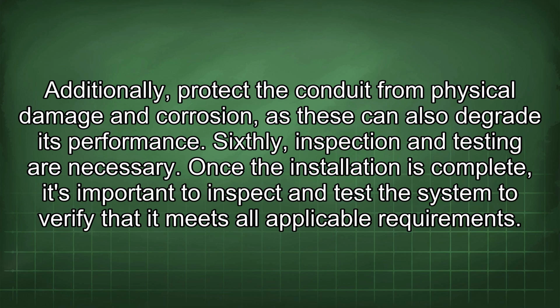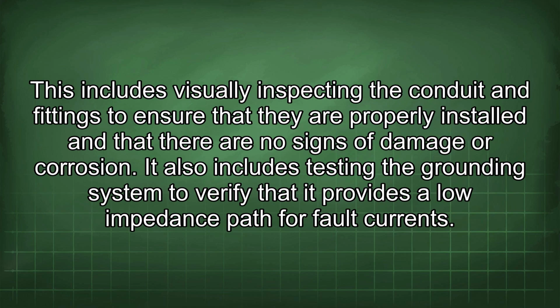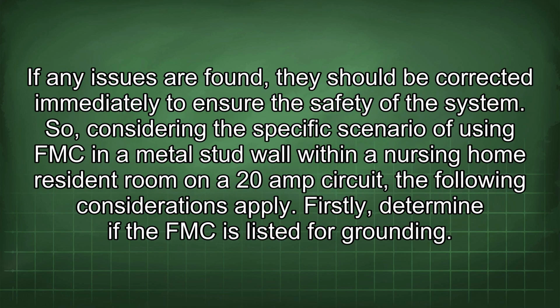Sixthly, inspection and testing are necessary. Once the installation is complete, it's important to inspect and test the system to verify that it meets all applicable requirements. This includes visually inspecting the conduit and fittings to ensure that they are properly installed and that there are no signs of damage or corrosion. It also includes testing the grounding system to verify that it provides a low impedance path for fault currents. If any issues are found, they should be corrected immediately to ensure the safety of the system.